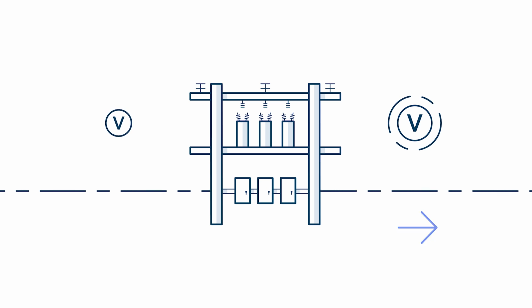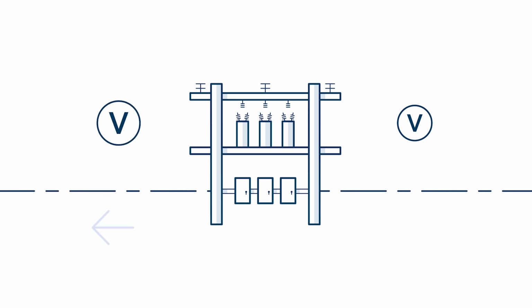One common solution is a bidirectional mode that measures power flow. When the voltage regulator control detects a reverse power flow, it switches direction so that it's correcting the voltage downstream from the new power source.